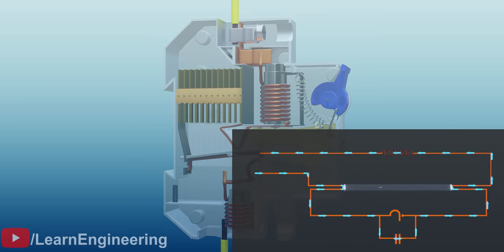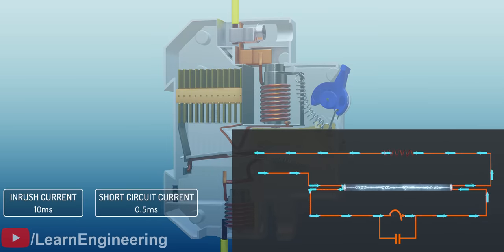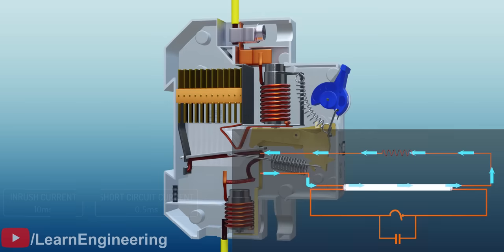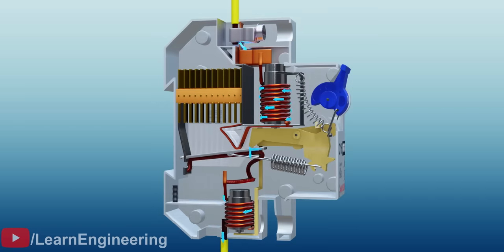Fluorescent tubes, for example, carry an inrush current during startup that maintains for about 10 milliseconds and then goes back to normal. Therefore, using a lower-rated electromagnet will cause the breaker to trip unnecessarily when you start electrical appliances.